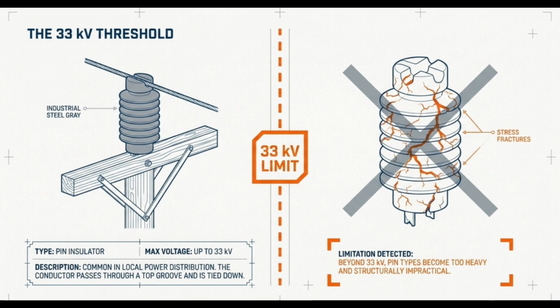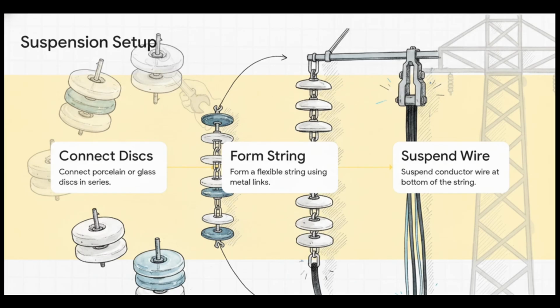We needed a better way to scale up. To blast past that 33 kV limit, engineers designed suspension insulators. The assembly is surprisingly simple, but totally ingenious. Step 1: you connect multiple porcelain or toughened glass insulator discs in a series. Step 2: you link them all together with metal joints to form a flexible hanging string. Step 3: you suspend the heavy conductor wire from the very bottom of this string, so it hangs vertically straight down from the tower arm, holding the live wire safely away from the metal structure.